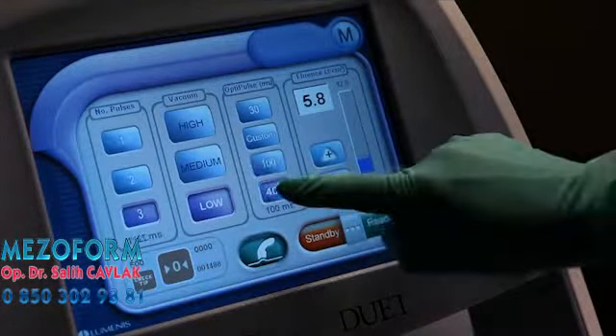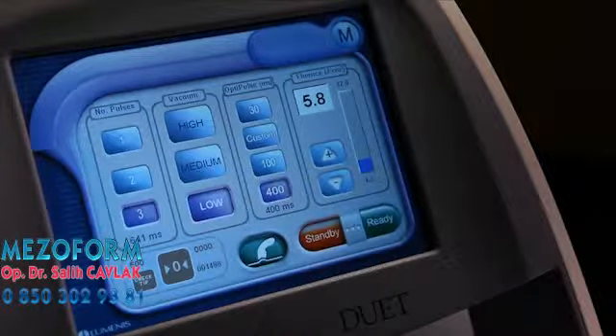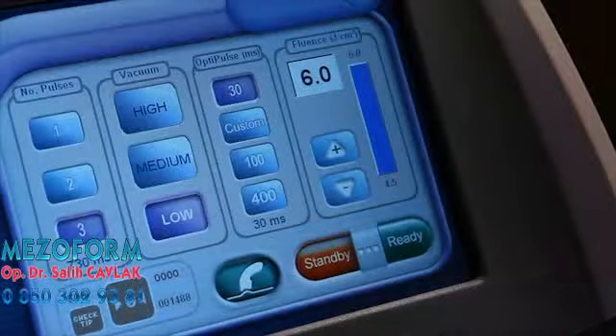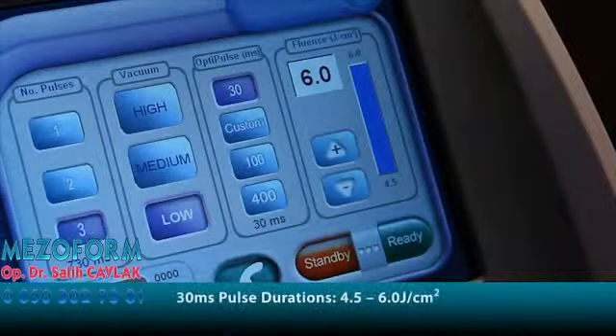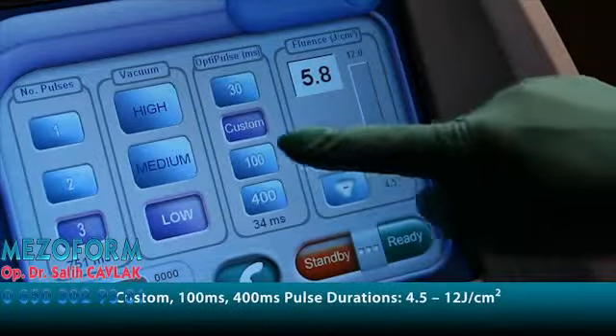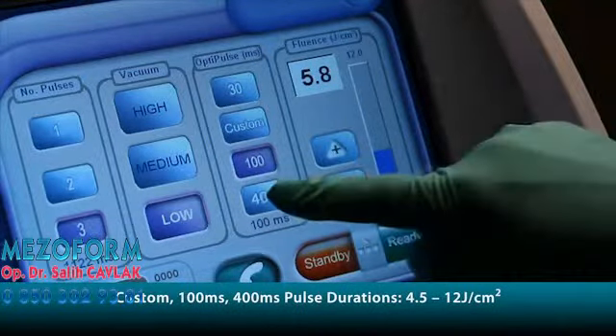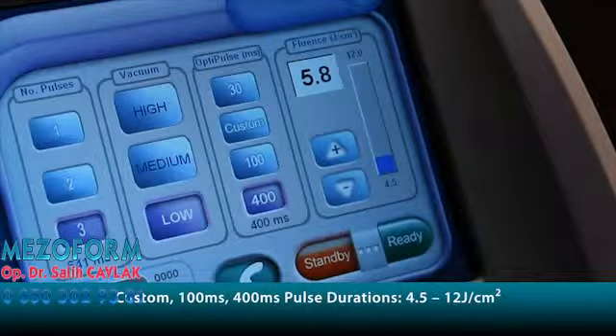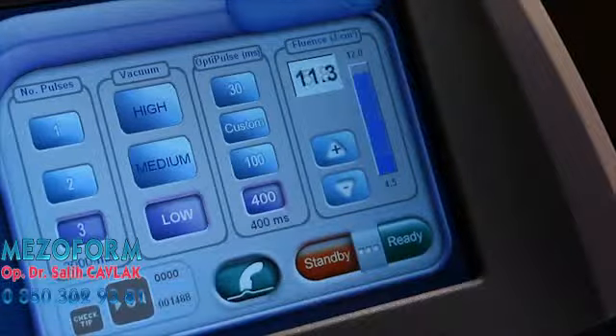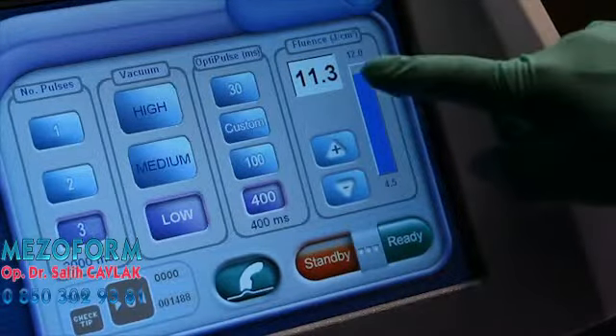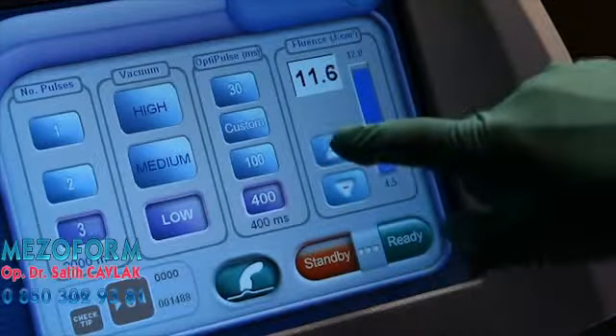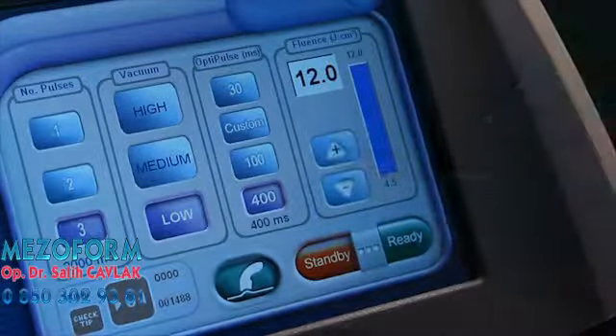100 millisecond and 400 millisecond pulse widths are typically used on tanned skin and darker skin types. The range of fluence is limited to 4.5 to 6 joules per centimeter squared when selecting the 30 millisecond pulse duration. Custom, 100 millisecond and 400 millisecond pulse durations have a range of fluence from 4.5 to 12 joules per centimeter squared. Skin types 1 to 3 usually require 9 joules per centimeter squared and above to produce permanent hair reduction.